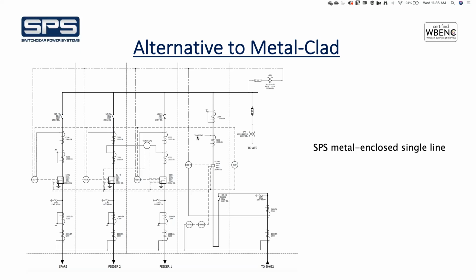So my follow-up question will be, except the draw out or non-draw out, what will be the other cons for the metal enclosed option compared to metal clad? What would be the other drawbacks, for instance? Well, we can epoxy coat and insulate the bus, which we do as a standard on this circuit breaker switchgear. The requirement to shroud all of the bus bars isn't there, and with the switches, it becomes more difficult to shroud the different potentials. But other than that, we think it's a great solution. I can't think of really anything off the top of my head that would be another drawback.